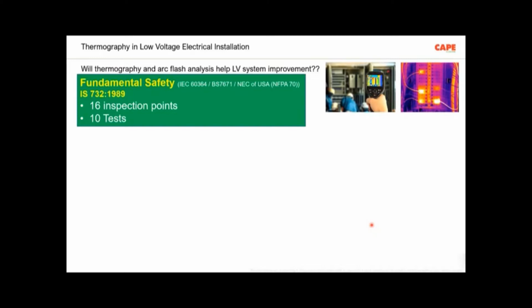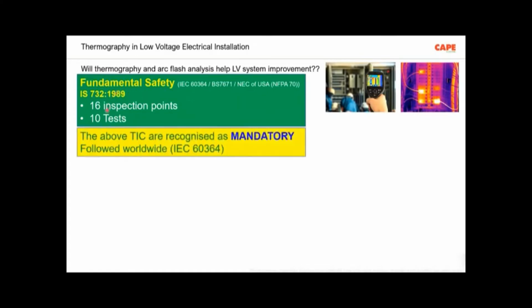In all these standards, of course, for us IS 732 is important. We are not bothered about the British and American standards; I am just showing you for your information. Don't follow British and American standards. We are Indians. We should respect and follow our standard. Now, to achieve fundamental safety, 16 inspection points and 10 tests are included in this standard. I repeat, 16 inspection points and 10 tests. If you are doing these testing, inspection, and certification (TIC) points, these are actually mandatory. These are recognized as mandatory safety measures, followed worldwide because IEC 60364 is followed across the globe as the basic electrical safety requirement.